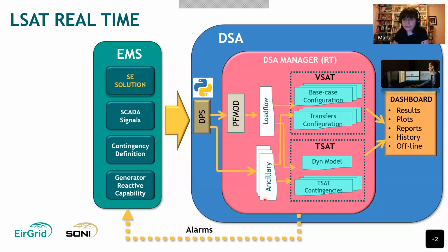We have a load flow and a number of ancillary files, which are used by two applications, VSAT for voltage stability and TSAT for transient stability. These files are combined with a number of other configuration and model files that live permanently in DSA. Once the computations are completed, voltage and transient security, the results are sent into a dashboard where we can have all the reports, plots, history, and we can access all the files and conduct additional offline analysis. And the loop is closed by the capability of sending alarms back into EMS results and alarms.